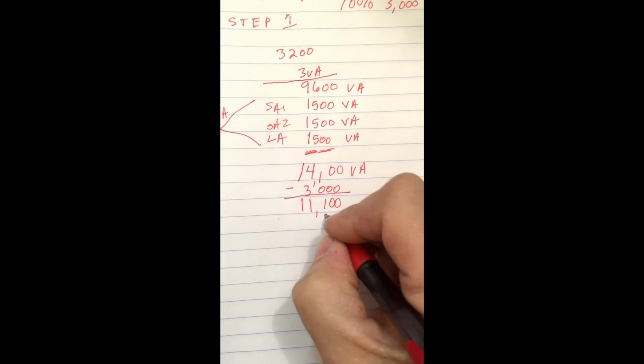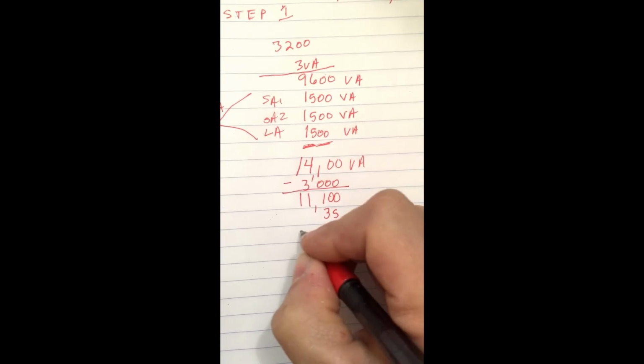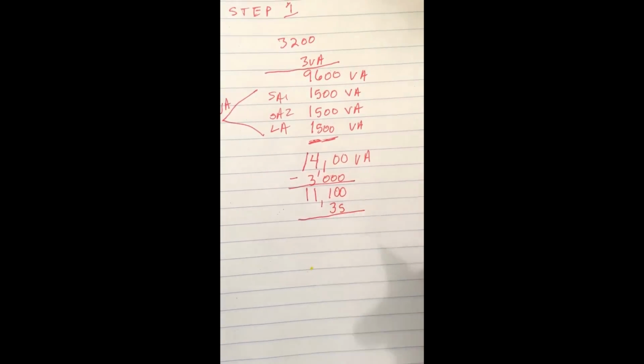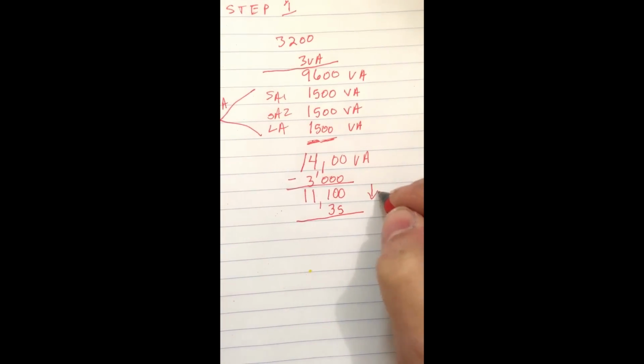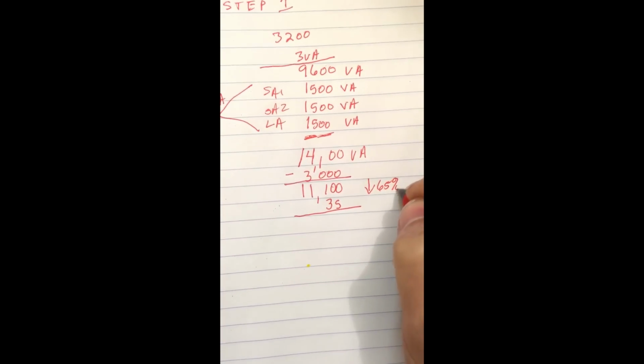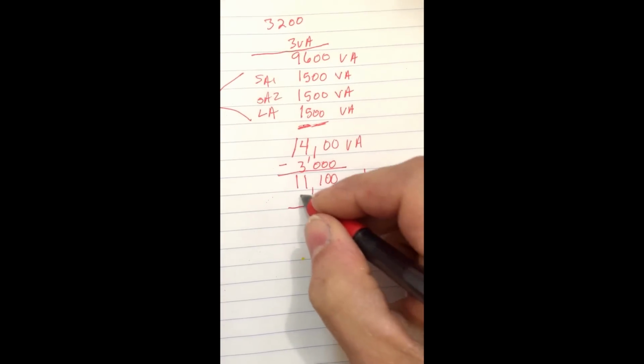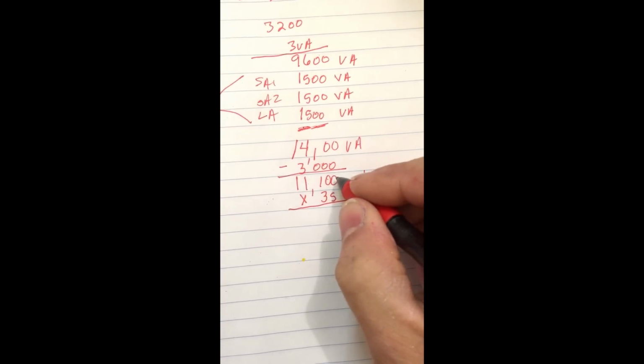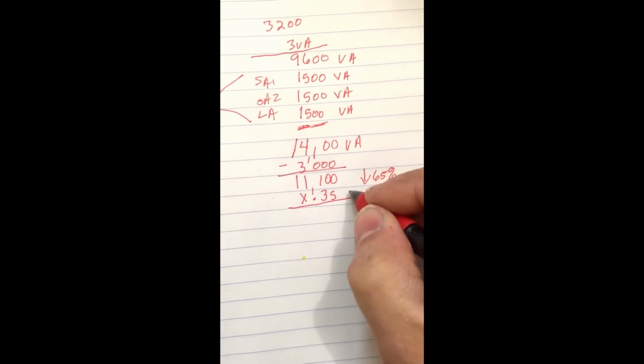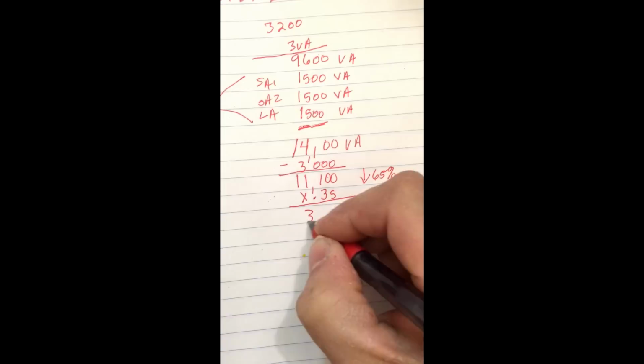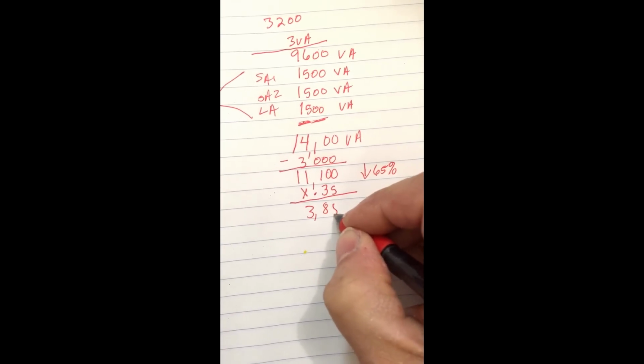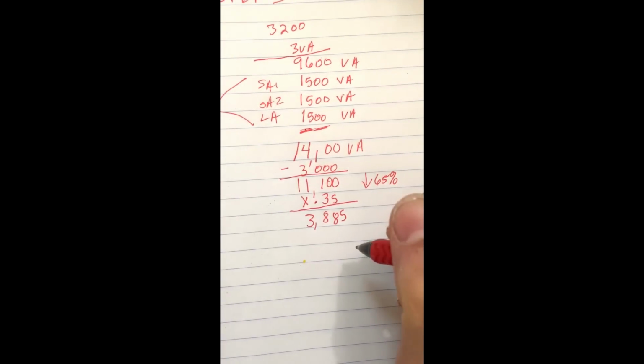So I'm going to take a derating of 35%. I'm going to keep 35% of this number, so what I'm really doing is discounting it by 65%. The math here is just on your calculator, 11,100 times 0.35, and you should get a value that's 3,885, if I'm not mistaken. Let me do that real quick on the calculator just to make sure.